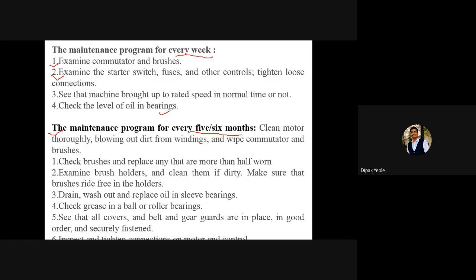Clean the motor thoroughly, blowing out the dirt from windings, wipe the commutator and brushes, check the brushes and replace any that are worn more than half. If they are broken or damaged, we have to replace the brushes. Examine the brush holders. For holding a lamp, we use a lamp holder. In the same way, for holding a brush, we use brush holders, and clean them if dirty. Make sure that the brushes ride free in the holders.